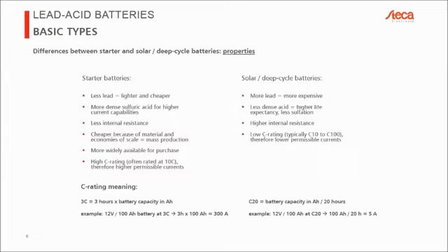The C rating is often a point of confusion for people, even in the solar industry, but it's actually relatively simple. I've put up the formulas at the bottom with an example. Car batteries are actually often rated at 10C. What does that mean? If we have the number before the C, this is the formula—let's take an example, 3C—it means 3 hours times the battery capacity in amp hours. So let's take an example: we have a 12 volt, 100 amp hour battery rated at 3C. Sometimes you have several ratings on a battery.